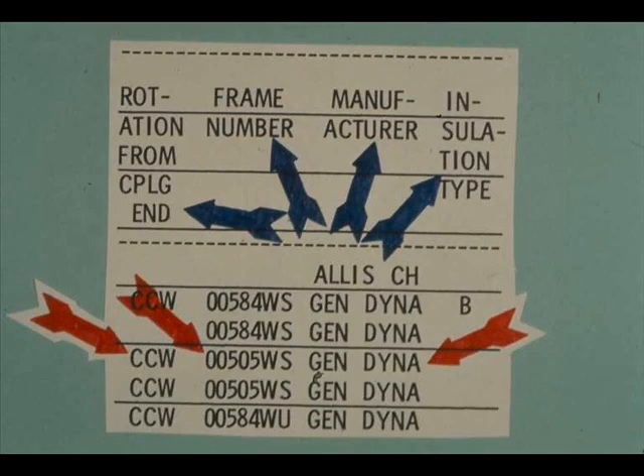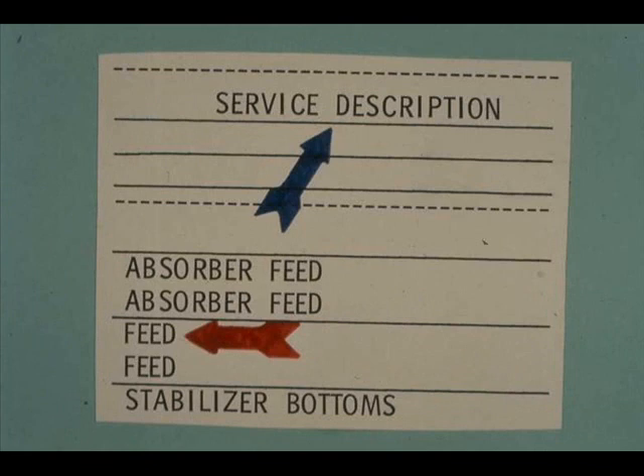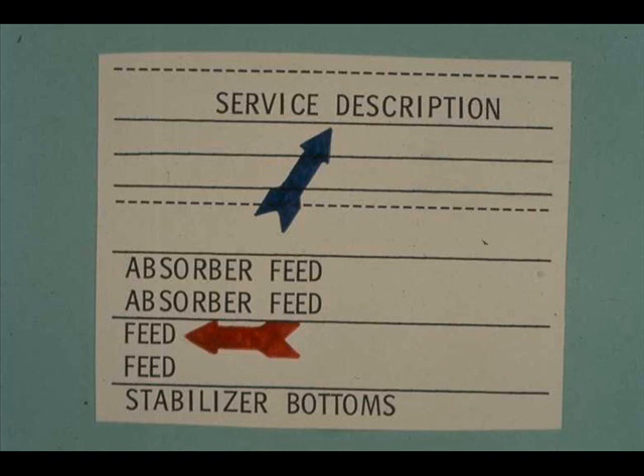Continuing across the page, column headings are rotation from coupling end, frame number, manufacturer, and insulation type. Our example motor rotates counterclockwise; its frame number is 505 WS; it was manufactured by General Dynamics; its insulation type is not listed. The next two column headings are enclosure type and unit or area — the unit is 2 PHLA, that is number 2 power former. The next column heading is service description — the motor we are following is in feed service. The last two column headings are unit item number and driven equipment; this motor has unit identification number M2A and drives a centrifugal pump, yard number 10648.